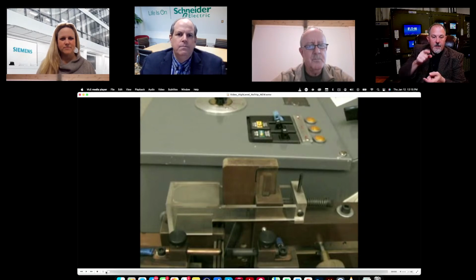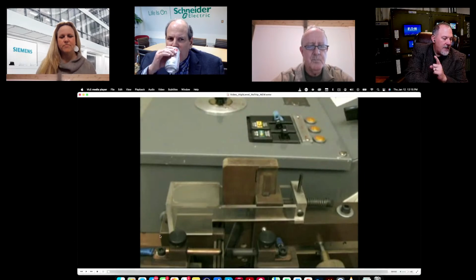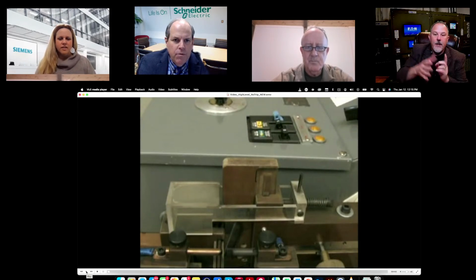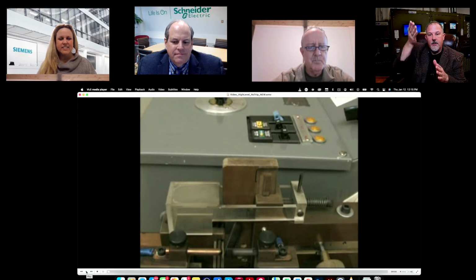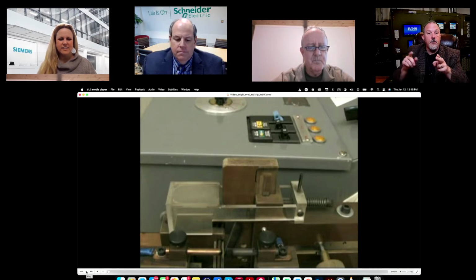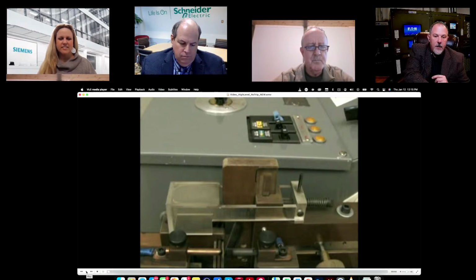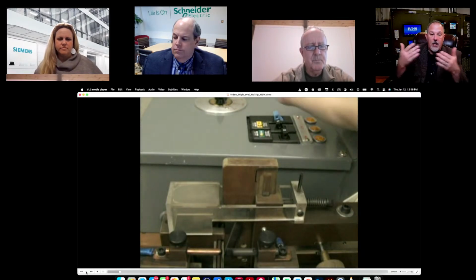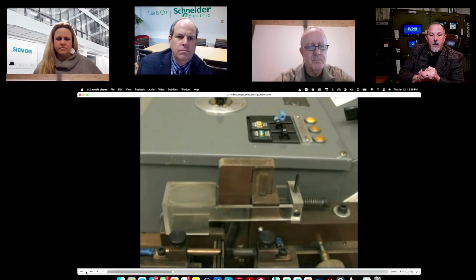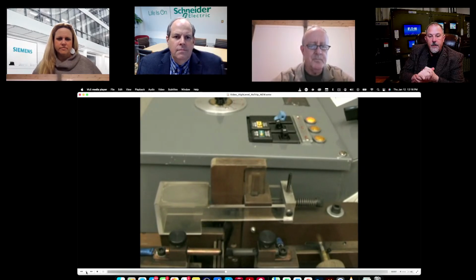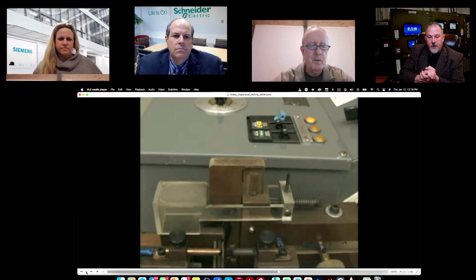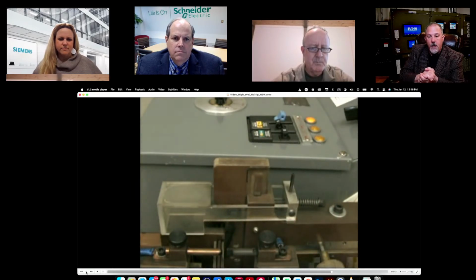So this video is basically showing what that gentleman was doing, though this is much safer. Let me tell you what you're seeing: down at the bottom you'll see some sparks, and there's a razor blade cutting into an SPT2 cord, like the conductor cord that would go to a lamp. In the video, this breaker with the blue handle will be turned on, a standard thermomagnetic circuit breaker, and it will basically not trip as the arc is being drawn. So power is turned onto the circuit, the razor blade is cutting into the conductor, and that breaker does not open.